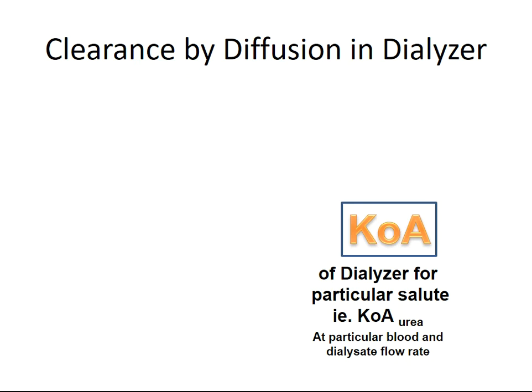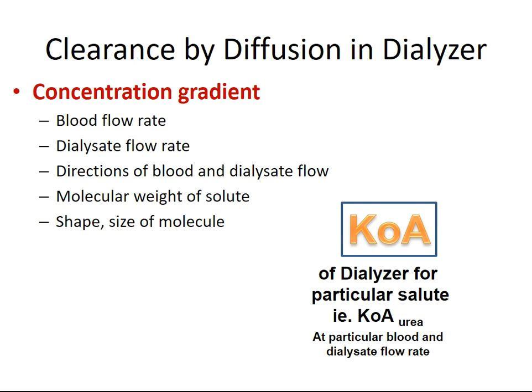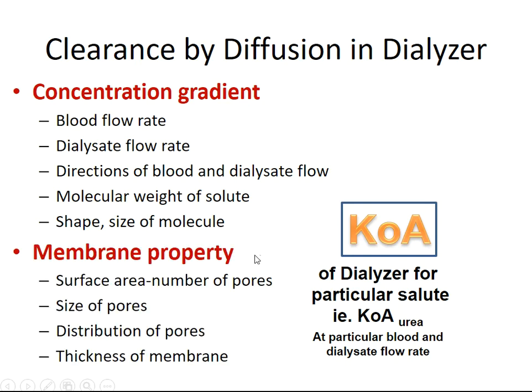Clearance by diffusion in the dialyzer depends on concentration gradient, blood flow rate, dialysate flow rate, direction of blood and dialysate flow, molecular weight of the solute, shape and size of the molecule, and membrane properties including surface area, number of pores, size of pores, distribution of pores, and thickness of the membrane. A thinner membrane has higher diffusive permeability.